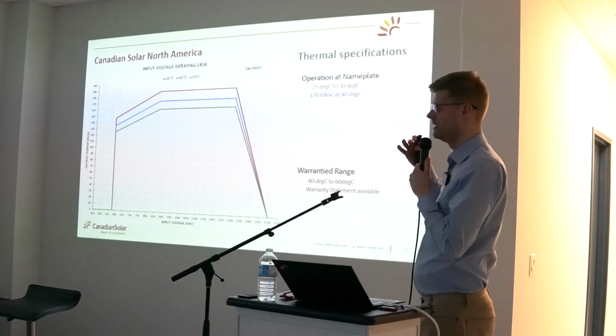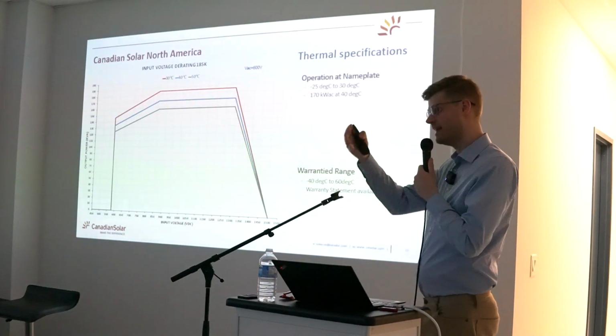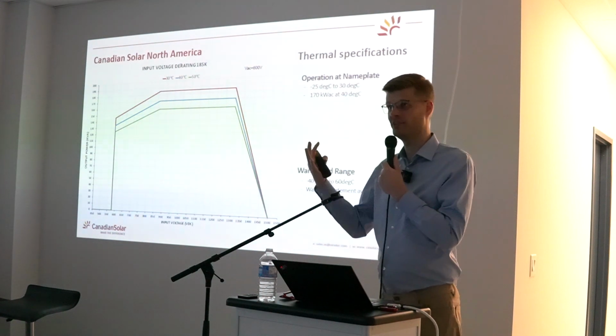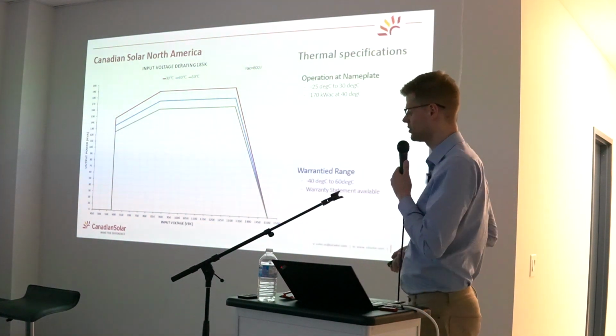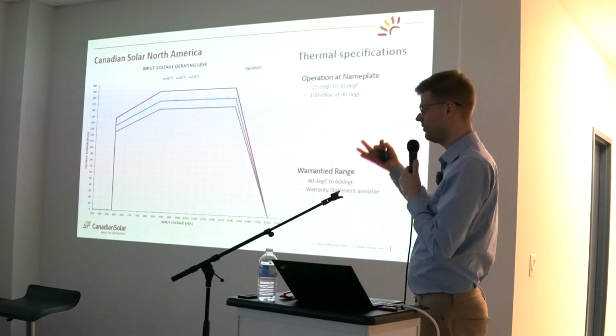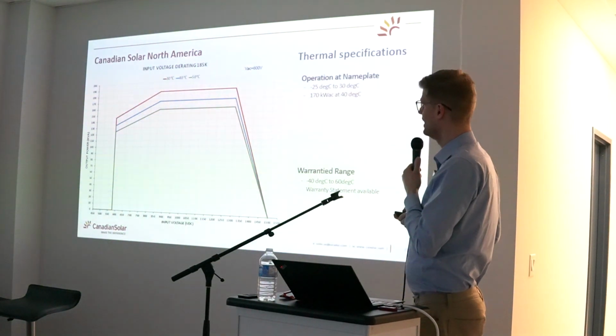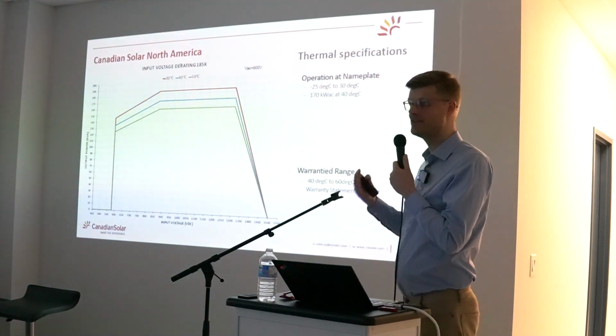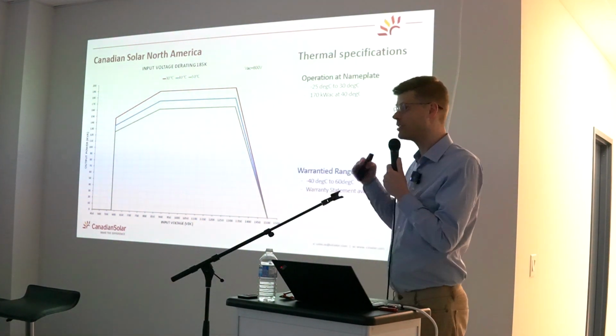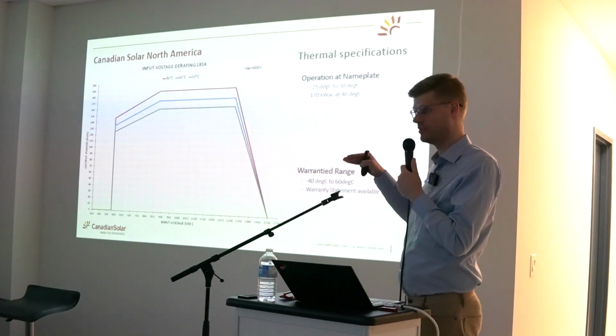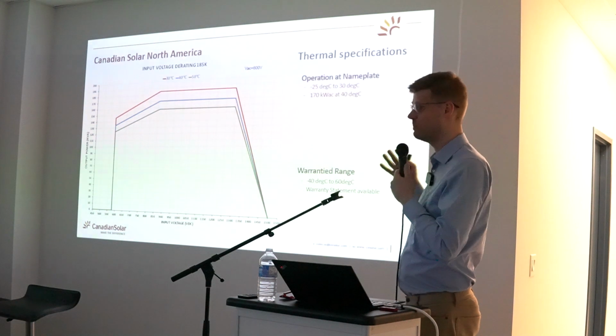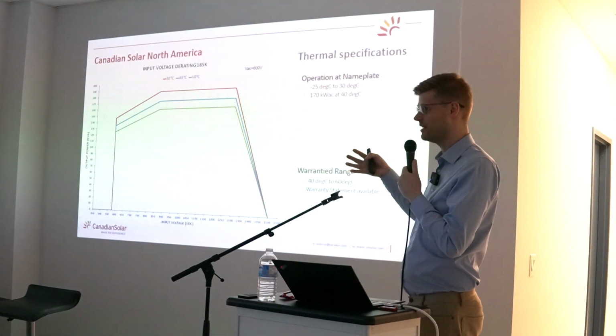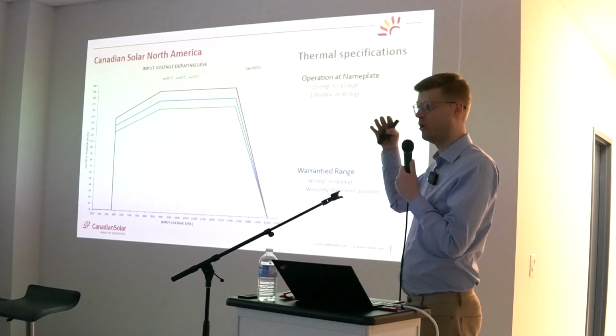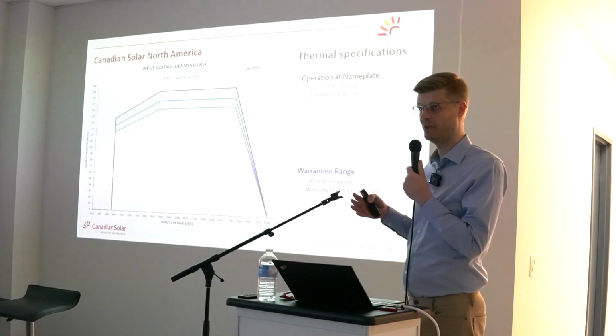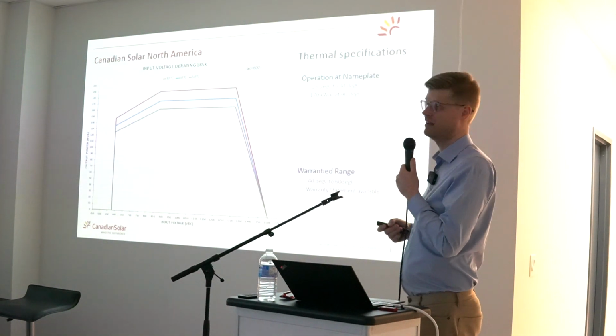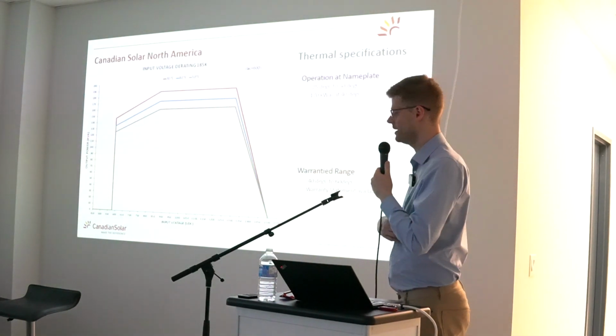The system is a fan-assisted system, so you have the heatsink on the back, and the fan will support the air as soon as there is a demand for additional cooling that a passive cooling with the air rising through the heatsink cannot provide. The 125 is a derated 185. So if you buy the 125, you're actually getting a 185 unit that is just software curtailed to 137.5 kilowatts, which means that you get the cooling method and the cooling system of the big unit, but you're only using it at whatever 2/3 of the actual power capability, which means that you can go significantly above the 30 degree without any limitations on the system.